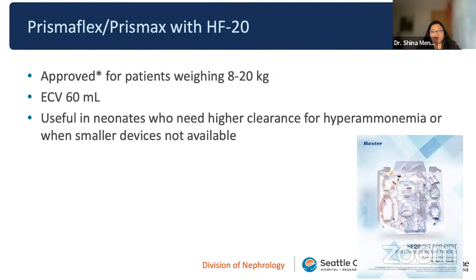So PrismaFlex or Prismax, I'll just go over these very briefly. They have a smaller filter, which had been available across the world for many years and has recently become available in the US. So when I say approved, that is just based on the US FDA approval for 8 to 20 kilos, but other places might have different regulatory guidelines for it. It has an extracorporeal volume of 60 ml and is really good in neonates who require higher clearance for ammonia or when smaller devices are not available.